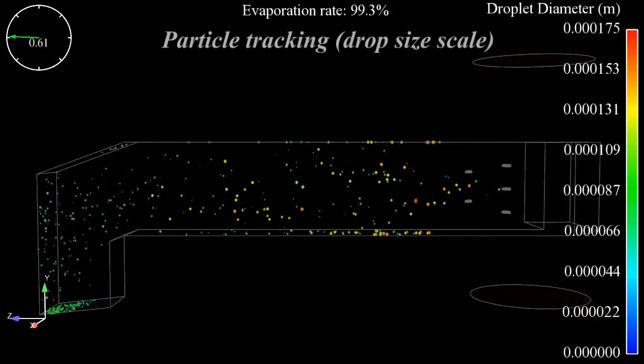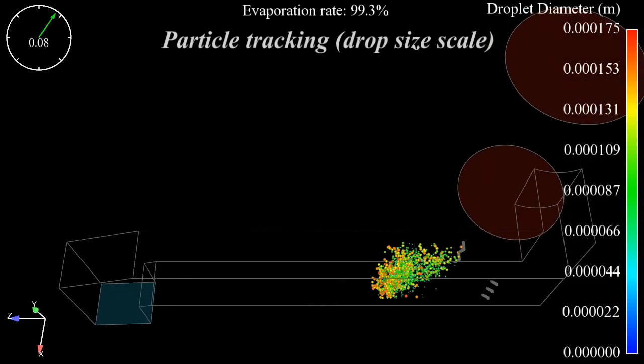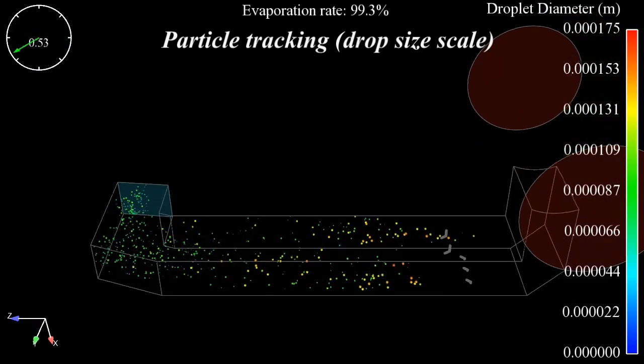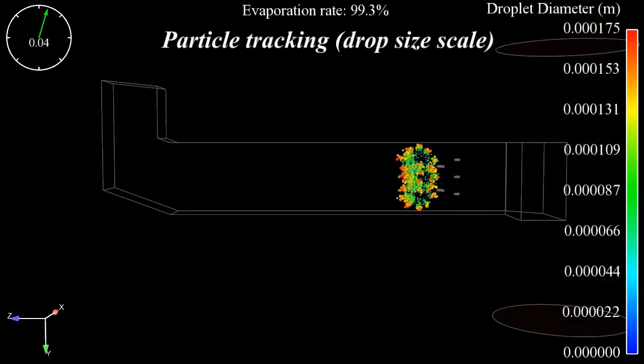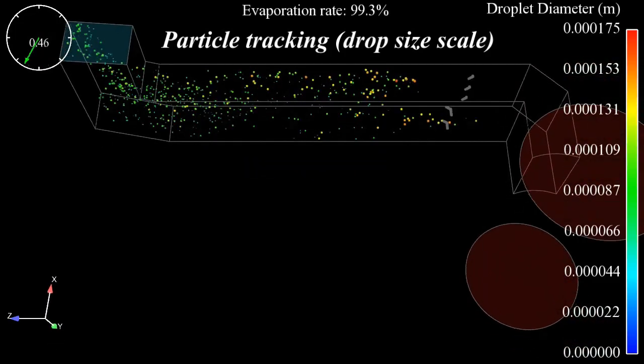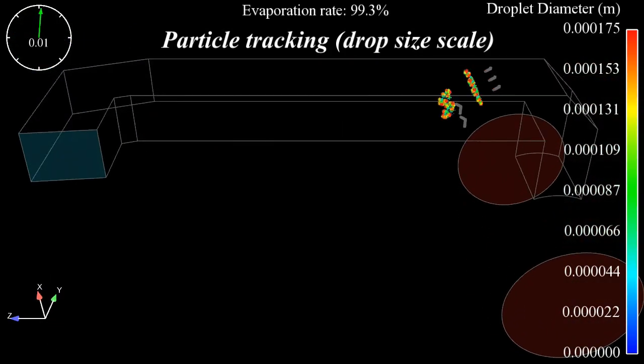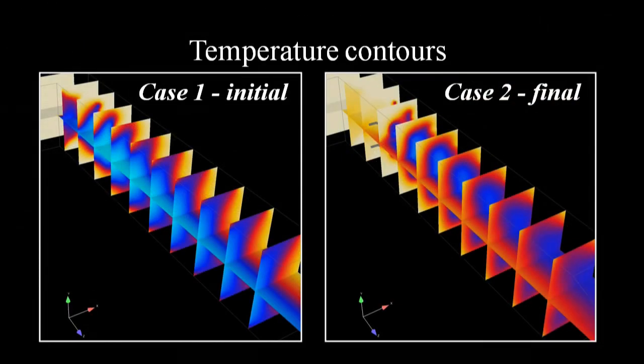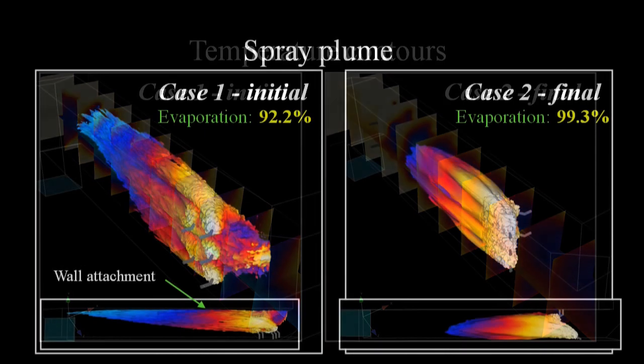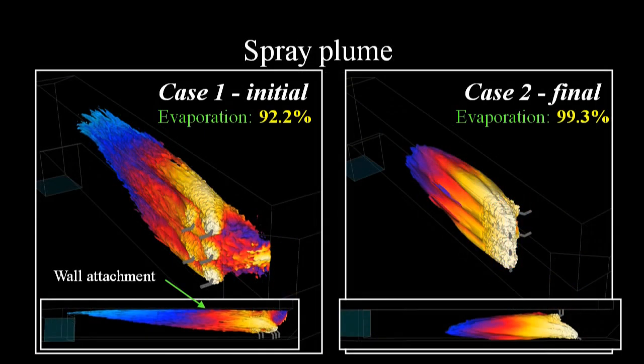Industry would have used the rule of thumb that 10 to 20 pipe diameters of straight length will be sufficient for achieving the desired cooling or mixing. 10 to 20 pipe diameters will not help in selecting the optimum nozzle placement. We have found that marrying our nozzle data with the Computational Fluid Dynamics Program enables us to challenge the rules of thumb that have been used throughout industry.